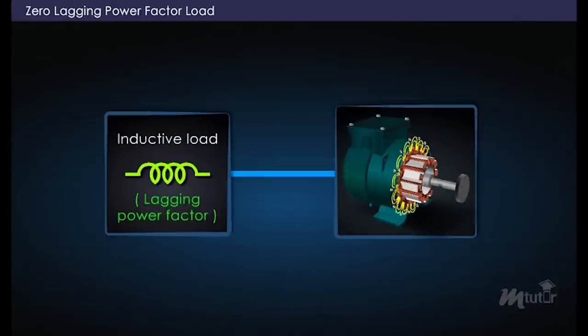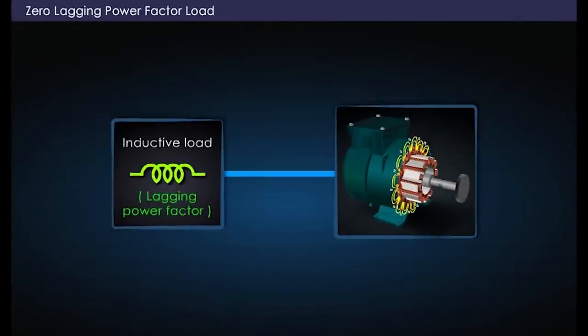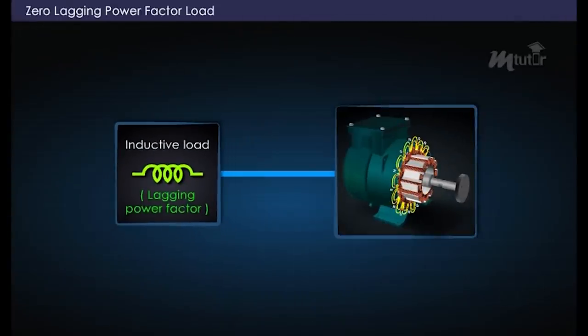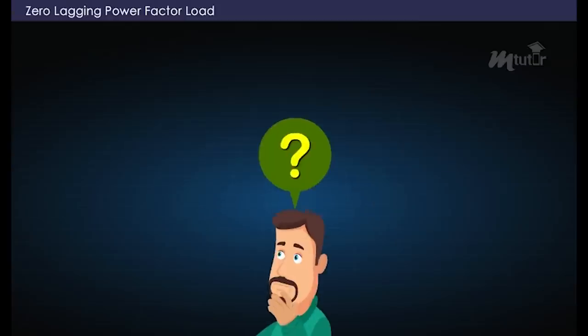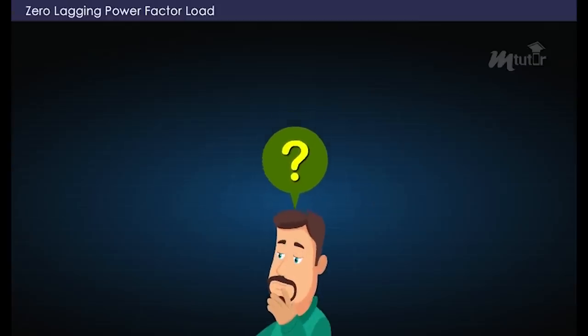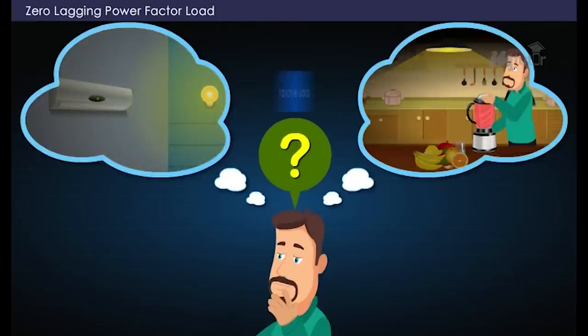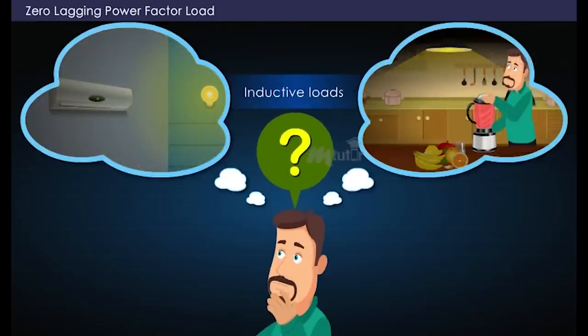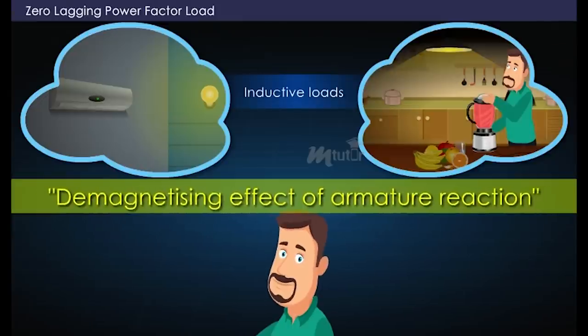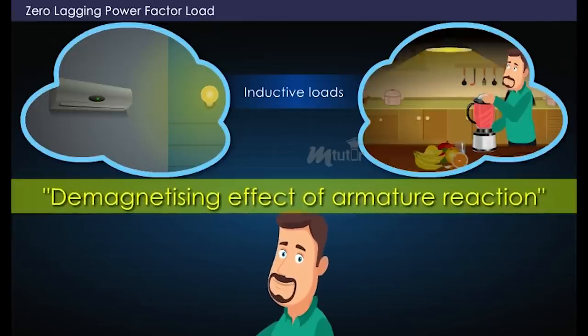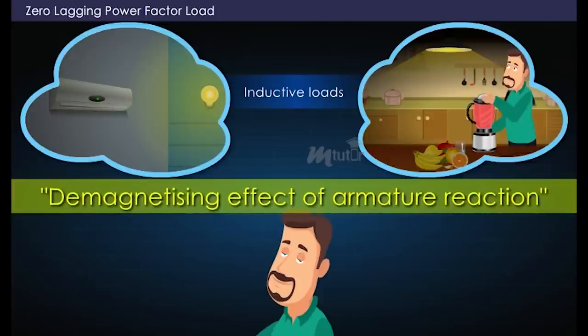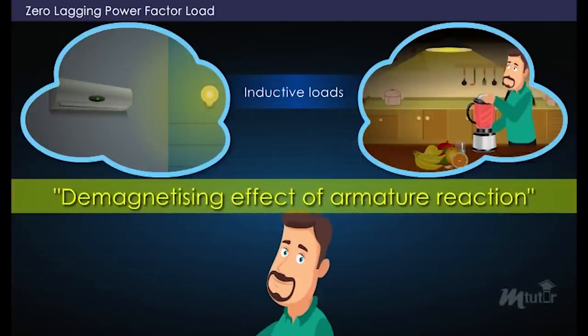For not purely lagging power factor loads, the armature reaction is partly demagnetizing. This allows us to answer Mr. Kamal's question: the loads he turned on were inductive with lagging power factor, which leads to the demagnetizing effect of armature reaction, resulting in a drop of the alternator voltage and causing the lights to dim.